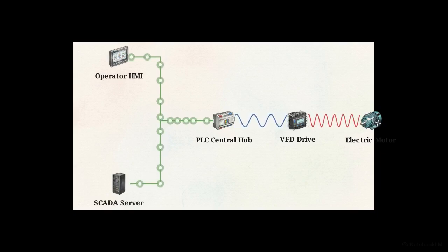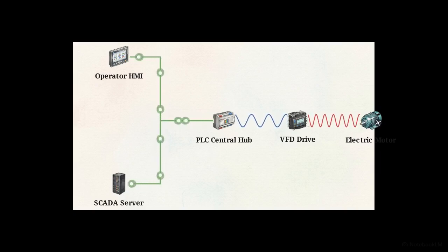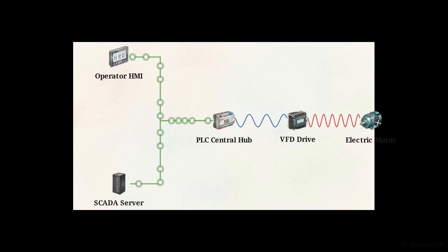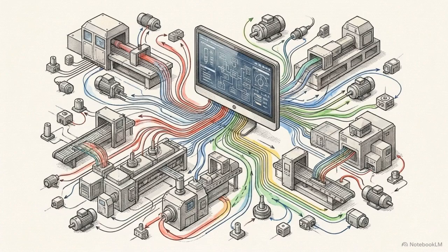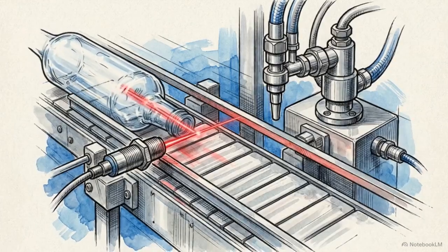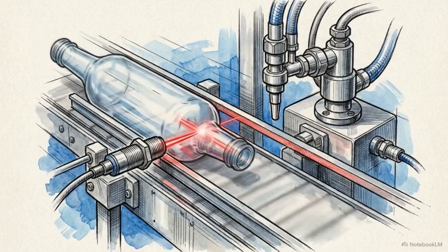Using high-level industrial protocols like Modbus TCP and Profinet, the PLC streams live production metrics directly to operator touchscreens and central SCADA servers. This final communication layer connects isolated motor starters and scattered sensors into a single unified data environment. Let's map that architecture onto a single real-time action on the bottling line.